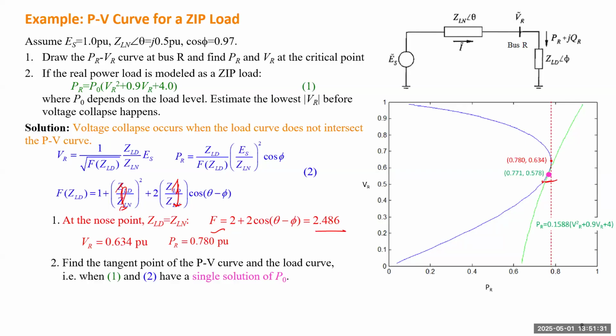So the tangent point is lower than the critical point. The critical point has power 0.78. The tangent point has 0.771, slightly lower than the critical point. So at that point, if I further increase the load, then collapse will happen. That will be the last point the system can operate. If you start from some initial loading condition, it will follow this curve. It can pass the nose point without issue until this tangent point. Then it won't have any solution. The system will collapse. So the voltage collapse point can be lower than the nose point.